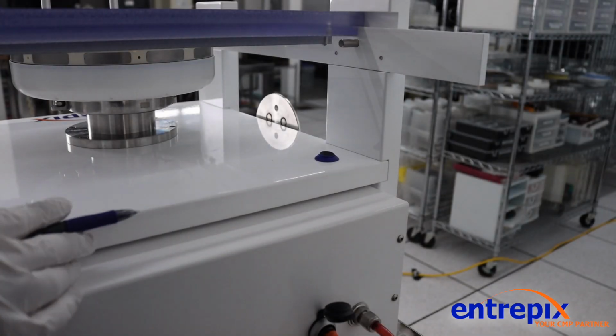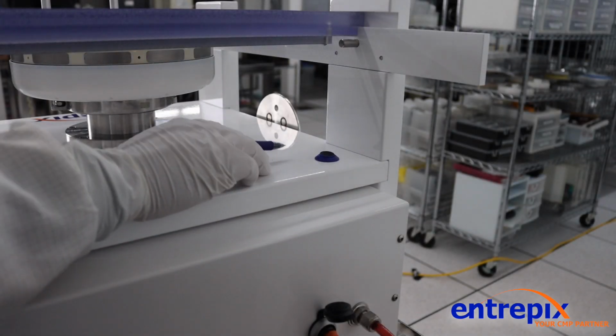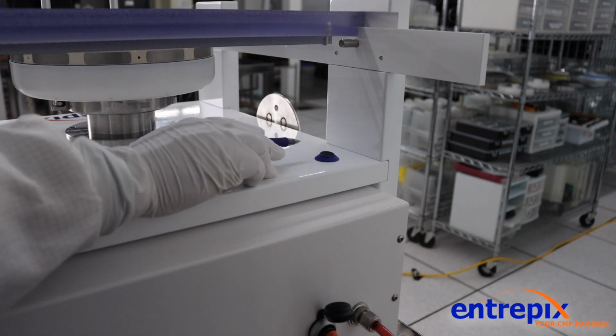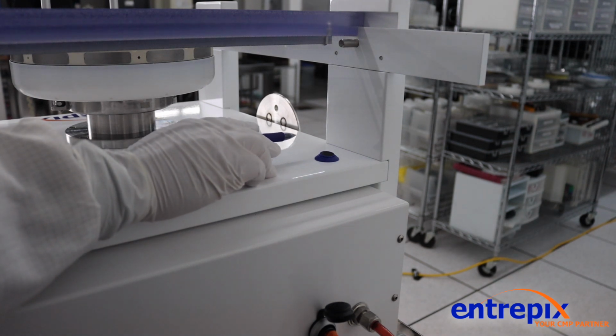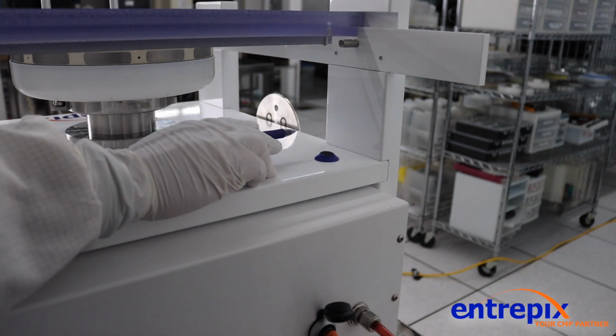Moving to the top portion of the tester, you will see an optical safety lid switch. During any time of operation, if the lid is detected as open, the tester will go into a safe condition by releasing all zone supply pressure and flashing a red lid open alarm text on the operator service screen.